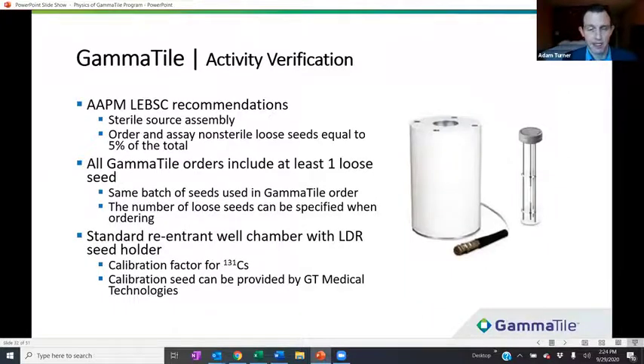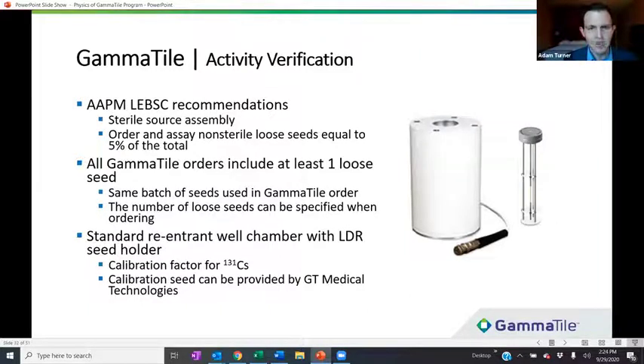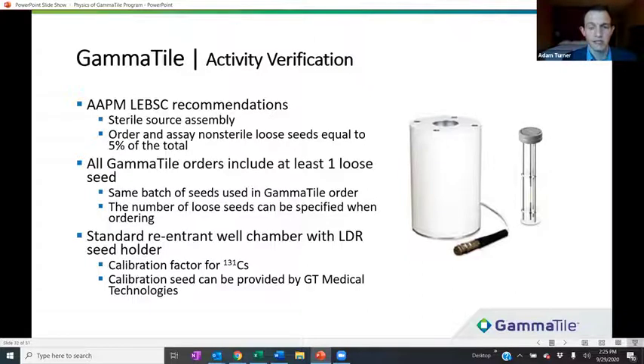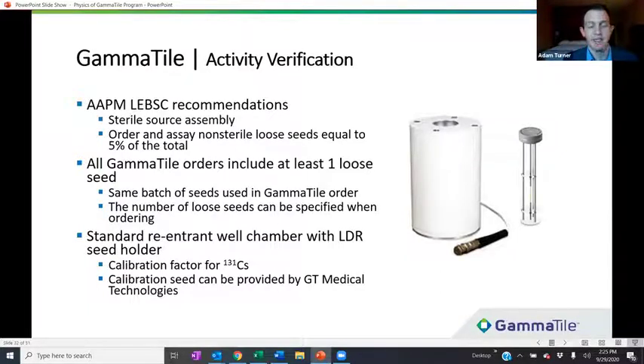Regarding activity verification, the AAPM low energy brachytherapy source calibration working group recommends that for sterile source assemblies like Gamma Tile, physicists order an assay of non-sterile loose seeds equal to about 5% of the total. All Gamma Tile orders will include at least one loose seed from the same batch of seeds used to build your tiles, and more can be specified when placing your order. We recommend using the standard methods of a re-entrant well chamber with an LDR seed holder and obtaining a calibration factor for Cesium-131. GT can help with calibration either through an accredited dose calibration laboratory or by providing a calibration seed with an exact activity certificate for in-house calibration.